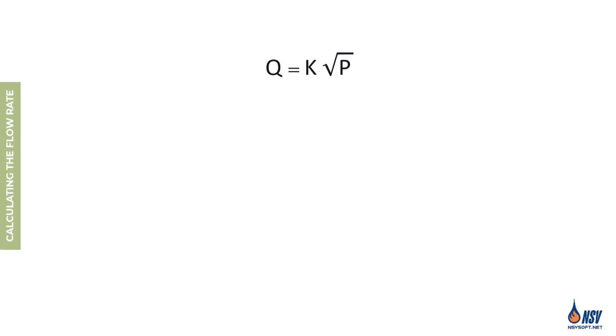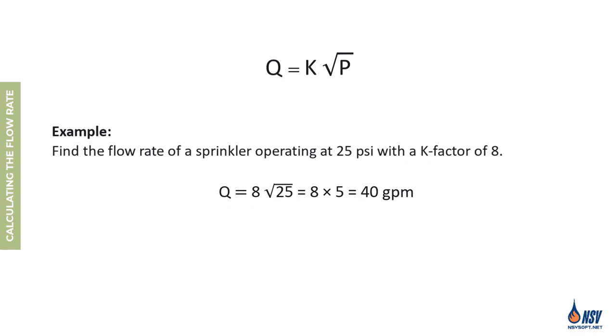In hydraulic calculations for fire sprinkler systems, we often encounter situations where the pressure and K factor of a sprinkler are known and we need to determine the discharge flow rate. For example, if the pressure behind the sprinkler is 25 psi and the K factor is 8, we can apply the formula Q = K × √P to find the flow rate.